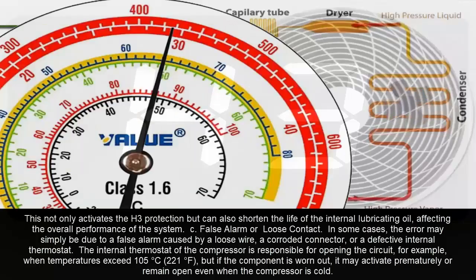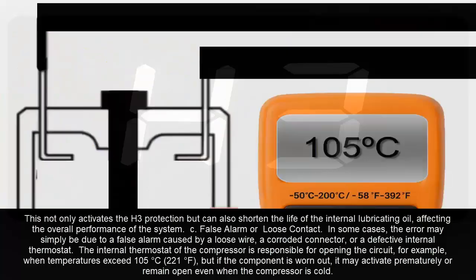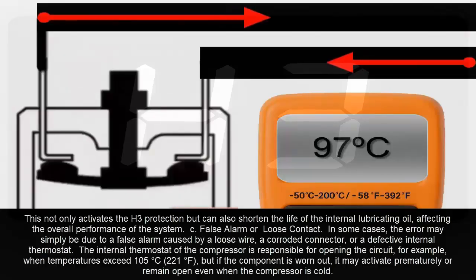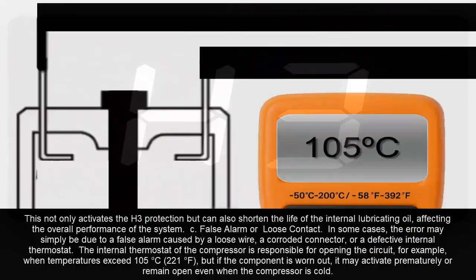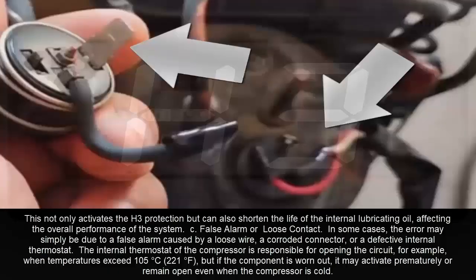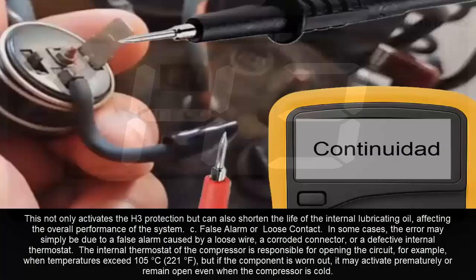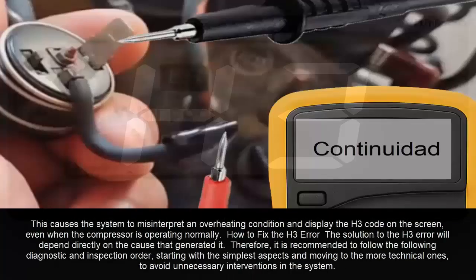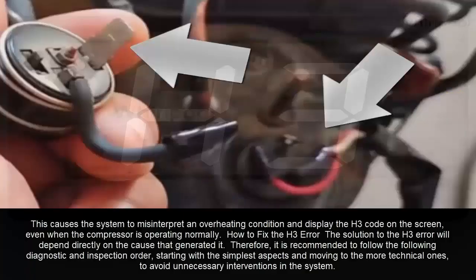C. False alarm or loose contact. In some cases, the error may simply be due to a false alarm caused by a loose wire, a corroded connector, or a defective internal thermostat. The internal thermostat of the compressor is responsible for opening the circuit, for example, when temperatures exceed 105 degrees Celsius, but if the component is worn out, it may activate prematurely or remain open even when the compressor is cold. This causes the system to misinterpret an overheating condition and display the H3 code on the screen, even when the compressor is operating normally.